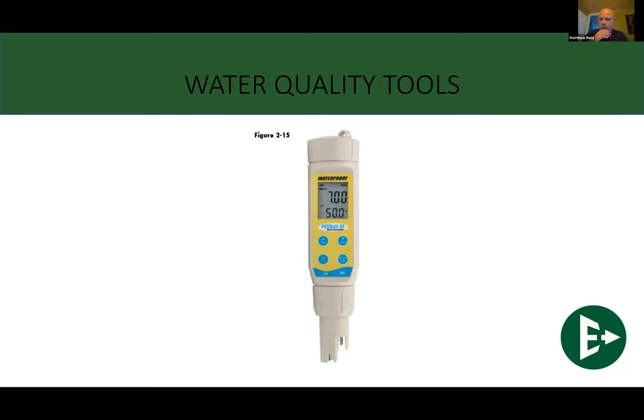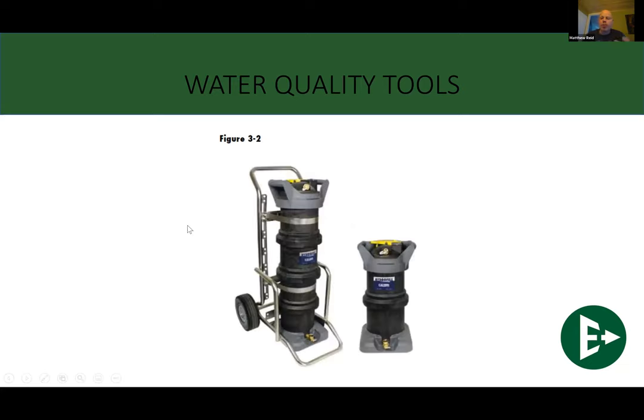And you can check this stuff. We get tools all over the place to check this stuff with. Standard pH tester, it tests pH and total dissolved solids. Buy them on Amazon for $20 or something like that. And check that water as it's going in. Make sure that it is in line with the manufacturer's recommendations. We also have portable demineralization filters. Essentially, this acts like a water softener, but it just is portable. It travels with you.